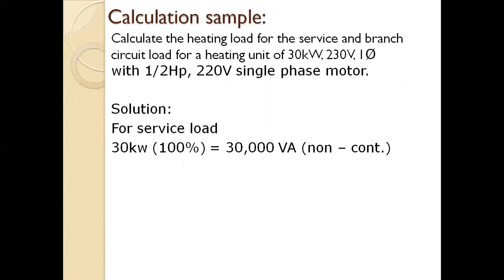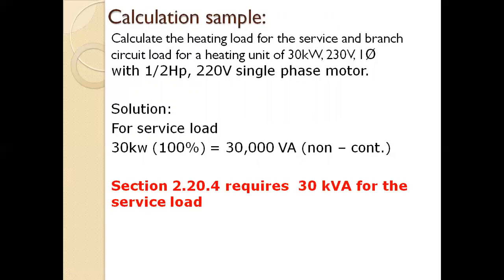Example number 1: calculate the heating load for the service and branch circuit load for a heating unit of 30 kilowatt, 230 volts, single phase, with a 1/2 horsepower, 220 volt single phase motor. For the service load, the heating load is considered non-continuous, so we multiply by 100%. For 30 kilowatt, we have 30,000 VA. Section 2.20.4 requires 30 kVA for the service load.